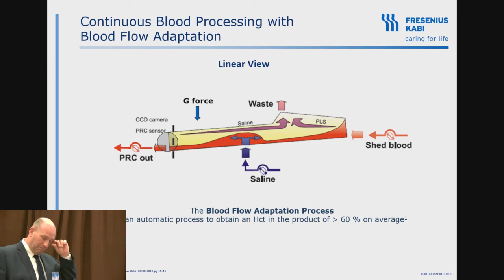And so as the fill level gets filled, it's maximizing the inflow. As it's filled and it starts removing, it'll then maximize it even more or decrease it, trying to maintain that. So that's our blood flow adaptation. The saline pump is on a ratio to the PRC pump, depending on the program you're using.